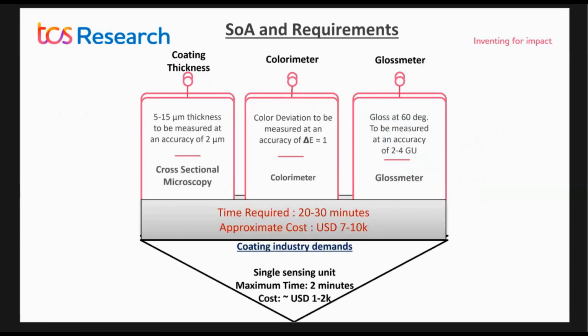The state of the art shows that for coating thickness measurement, approximately 5 to 15 micrometers of thickness has to be measured very accurately, at an accuracy of 2 micrometers. Presently it is done with the help of cross-sectional microscopy. A color meter is used for color deviation, and a gloss meter for gloss deviation, with a delta E of 1 and 2 to 4 gloss units. The time required is 20 to 30 minutes, and the approximate cost of all three instruments is 7 to 10K USD.